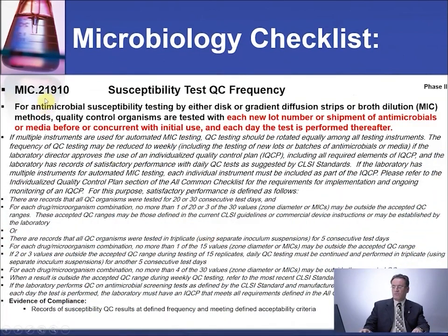For MICRO.21910, susceptibility test QC frequency, you need to do the QC on each lot number or shipment of antimicrobial or media before or concurrently with the initial use, and each day the test is performed thereafter.